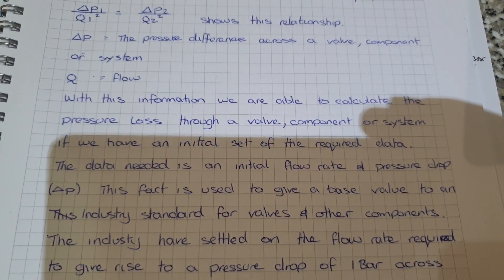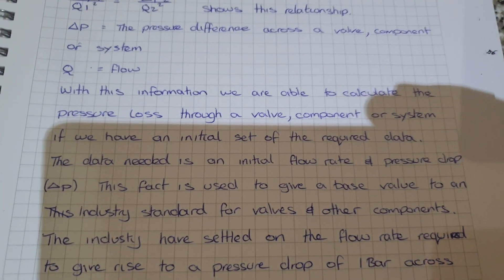Delta P being the pressure difference across a valve, component, or system, and Q equaling the flow. For this, the pressure difference is in bar and the flow is in cubic meters per hour. With this information, we're able to calculate the pressure loss through a valve, component, or system if we have an initial set of the required data.